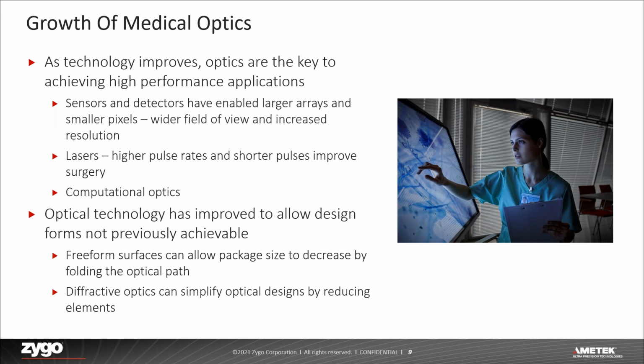As with all technologies, medical optics are being continuously improved with new technology. In recent years, we've seen detectors have larger areas and reduced pixel sizes. When using the same optical system with larger detectors, you will see an increase in the field of view. Decreasing the pixel size with the same optical system will allow an increase in the resolution.